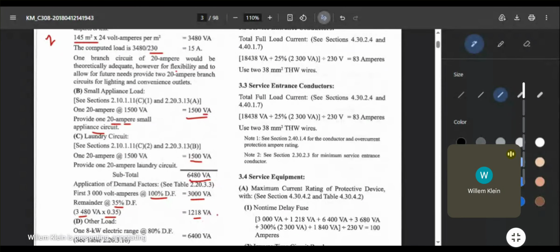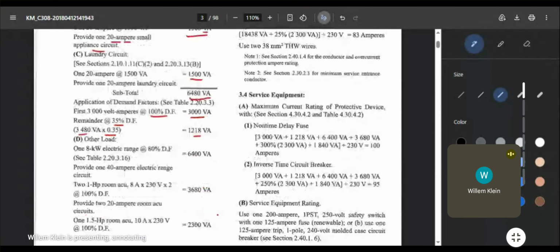And after that, let's see the other loads which make it more than 6 circuits. Again, these loads are all individual circuits, so they will have their own circuit breakers. So for example, you have one 8 kilowatt electric range. When we say electric range, that is a cooking range that is electric, with the induction cooker and electric oven, something like that. So your 8 kilowatt electric range is already taken from the table. So you will use 80% demand factor for that.